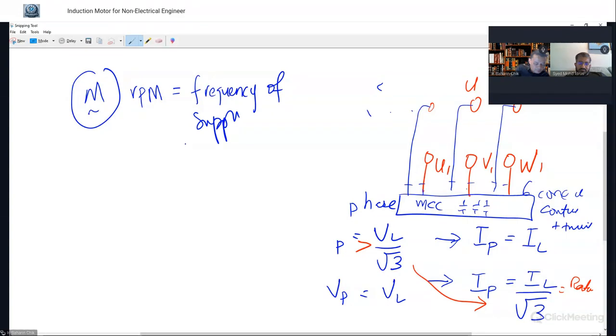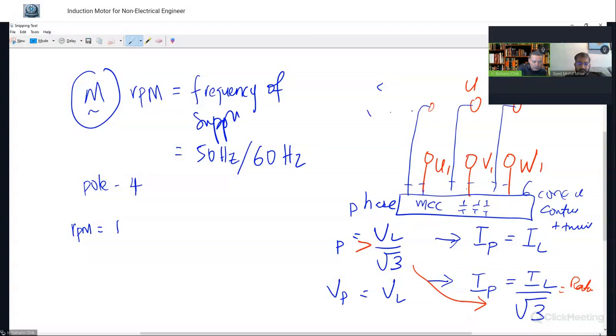So the maximum frequency, for example, if your grid is 50 hertz, it can go up to 50 hertz, or 60 hertz, then it can go up to 60 hertz. Now, for the RPM, it depends on the pole. Pole, we saw just now, right? If we have a 4-pole machine, then the RPM will be 120 times, for example, 50 or 60, then divided by the pole.